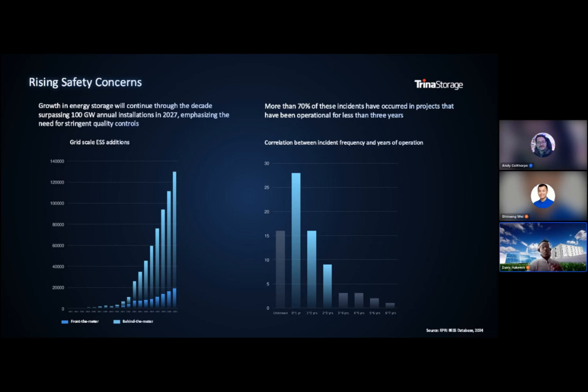Batteries are no more worse-offending than other equipment we've been operating for a very long time. NFPA did a study in 2023 that concluded batteries have generally seen fewer events than things like transformers on site or switchgear. So it's definitely an important thing to consider, and for us it's a priority—something we absolutely focus on all the time.